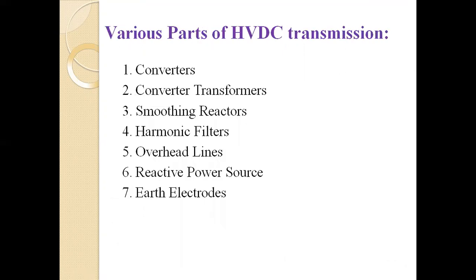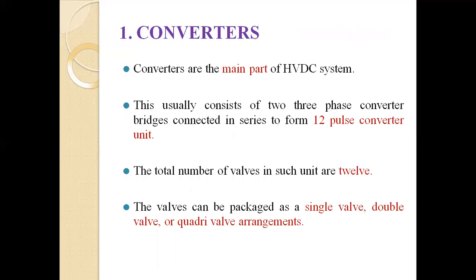So what are the various parts of the HVDC system? First is the converter, second is the converter transformer, third is the smoothing reactor, fourth is the harmonics filter, fifth is the overhead lines, sixth is the reactive power source, and last is the earth electrode. So these are the parts.